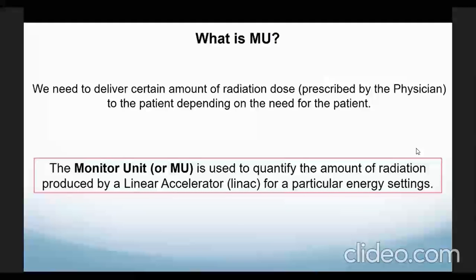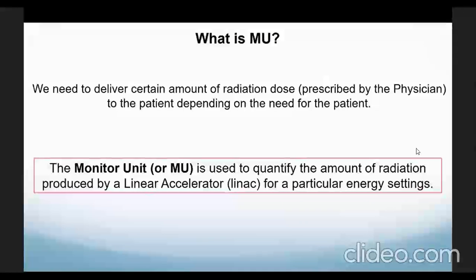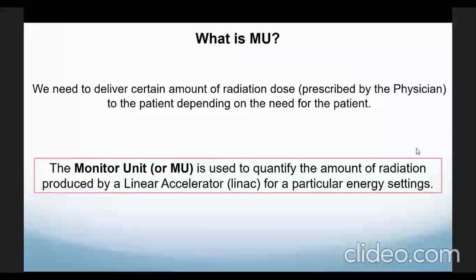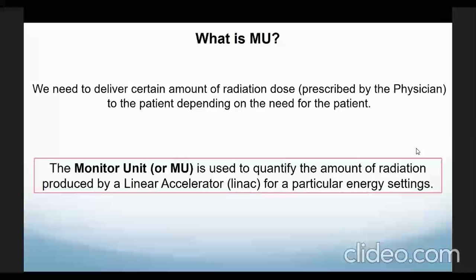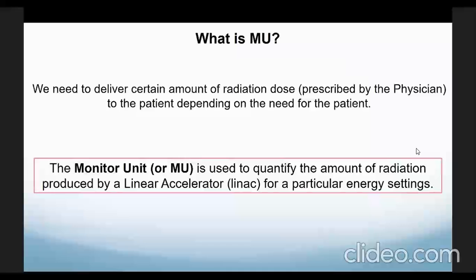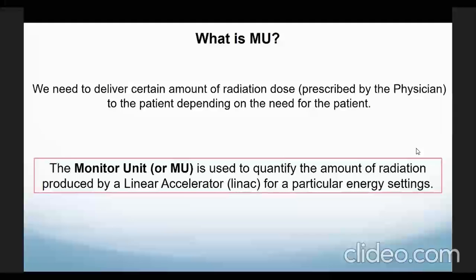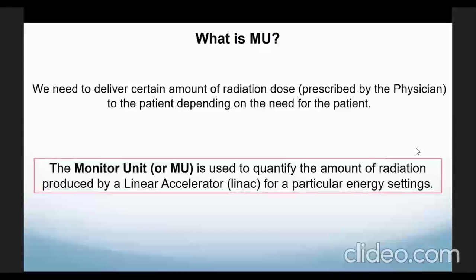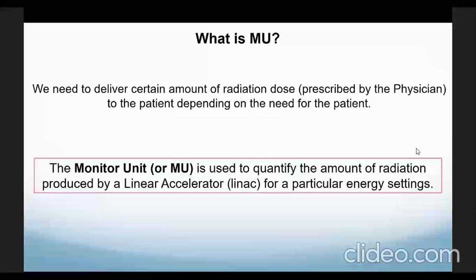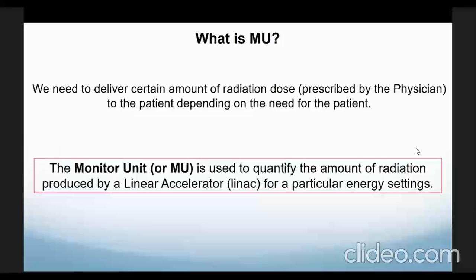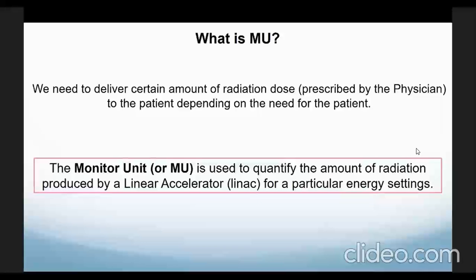The first question is: what is MU? We need to deliver a certain amount of radiation dose, which will be prescribed by the physician to the patient depending on their need. The machine can deliver radiation but does not know how much it is giving. So we need to relate the output of the machine to some quantity of radiation — how much we are giving to the patient. The monitor unit is used to quantify the amount of radiation produced by a linear accelerator for a particular energy setting.